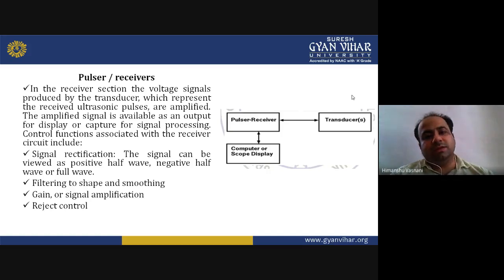Now in the receiver section, the voltage signals produced by the transducer, which represent the received ultrasonic pulses, are amplified. The amplified signal is available as an output for display, capture, or signal processing. Control functions associated with the receiver circuit include signal rectification. The signal can be viewed as a positive half wave, negative half wave, or full wave, as shown previously in the diagram. Then there is filtering to shape and smooth the signal, and gain or signal amplification, along with the reject control.